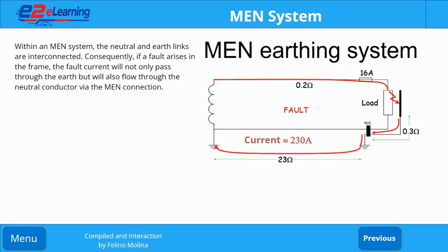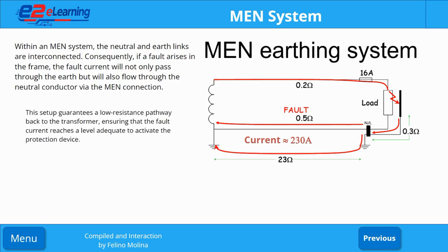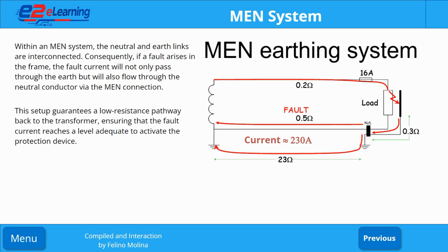Within an MEN system, the neutral and earth links are interconnected. Consequently, if a fault arises in the frame, the fault current will not only pass through the earth, but will also flow through the neutral conductor via the MEN connection. This setup guarantees a low-resistance pathway back to the transformer, ensuring that the fault current reaches a level adequate to activate the protection device.